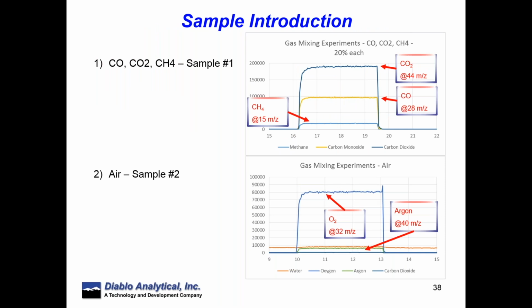So in this case here, you can see that we have a sample being introduced, and we're looking at CO, CO2, and methane, and that's 20% of each. And then we have an experiment where we're looking at air, oxygen, and argon. And in that experiment, you can see the amber line is water. And so we want to remember that we always have a trace level of water present in the mass spectrometer at all times. And again, that's one of the things that makes quantitation of water more challenging by mass spectrometry.